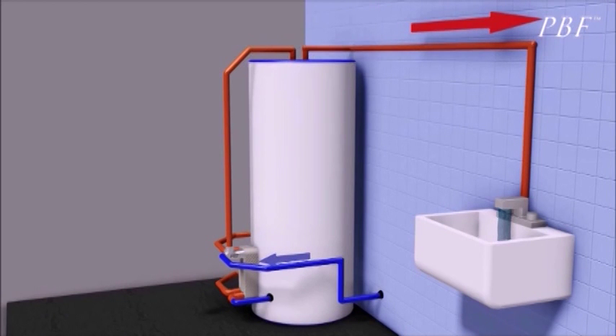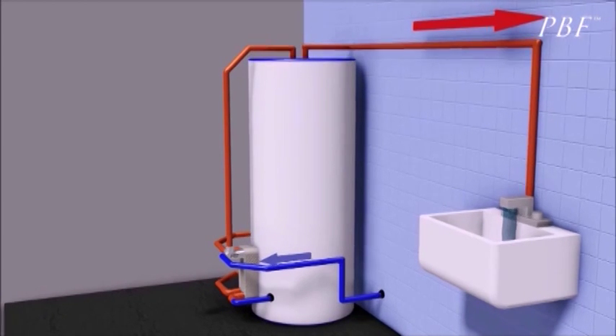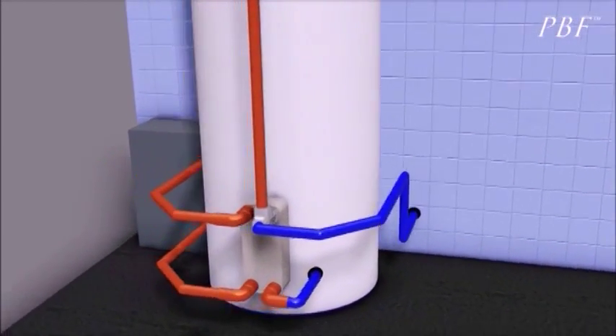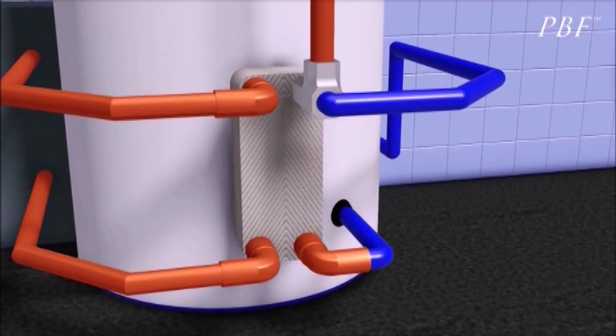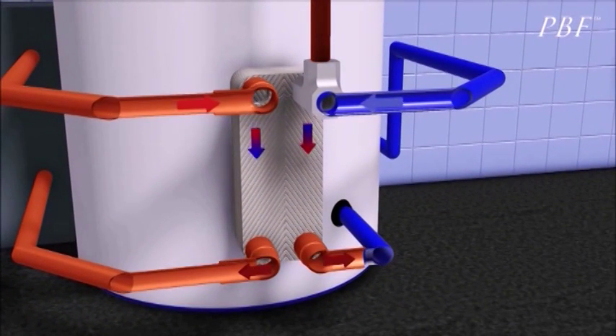Heat exchangers, this one here is a plate heat exchanger. They're very robust, inexpensive to manufacture, very small, compact, and efficient, but they have one key design flaw, which is the water that we drink has a lot of minerals in it. When you heat that water up, those minerals will precipitate out of the water and stick to the sides of the heat exchanger. As you can see, the plates here are nice and clean and shiny.